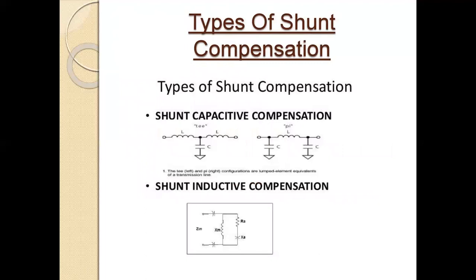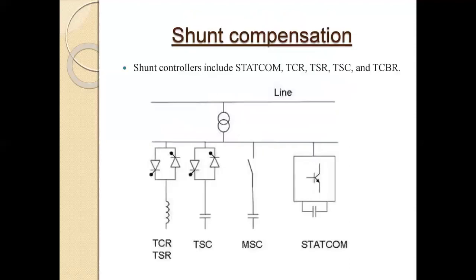The first type of shunt compensation is capacitive shunt compensation. In this figure, there is a T-type construction and here a pi-type line. In the T-type line, we connect the capacitor with the shunt connected transmission line, and it provides reactive power in the transmission line. STATCOM, TCR, TSR, TSC, and TCBR are examples of shunt compensation.